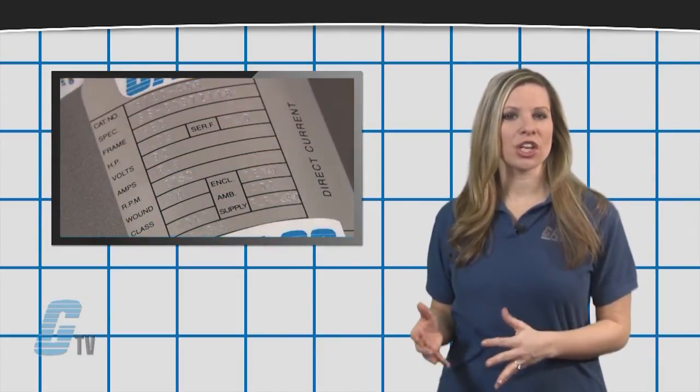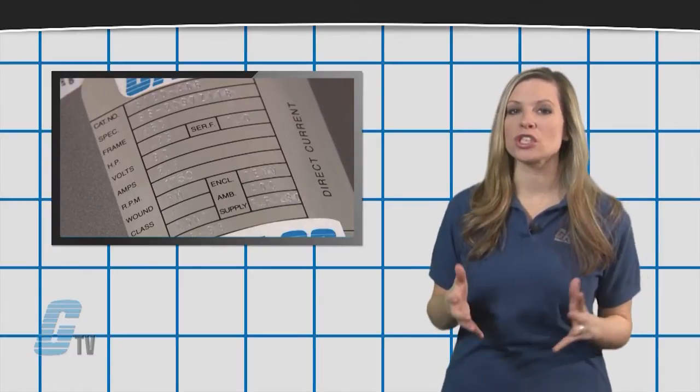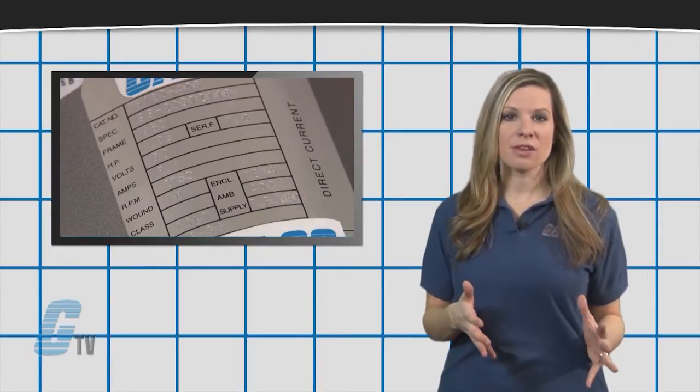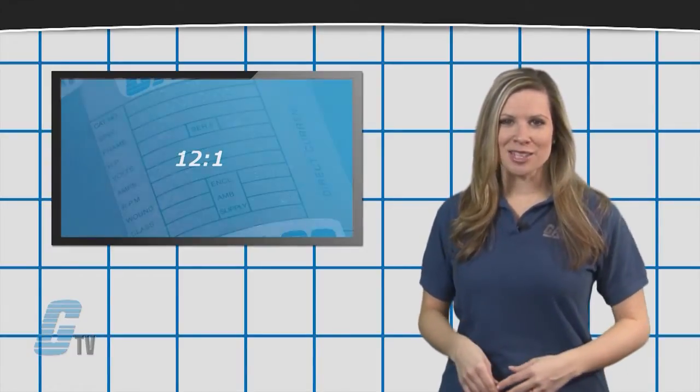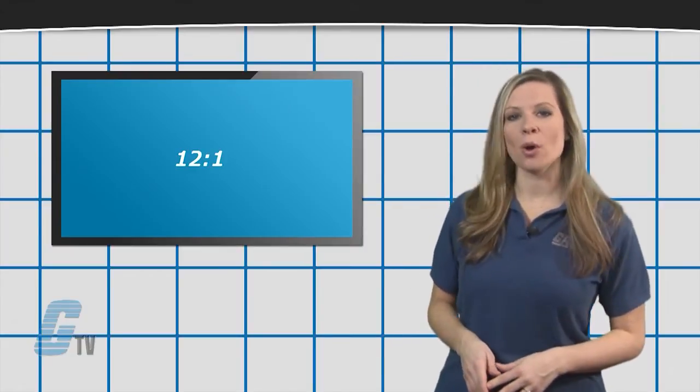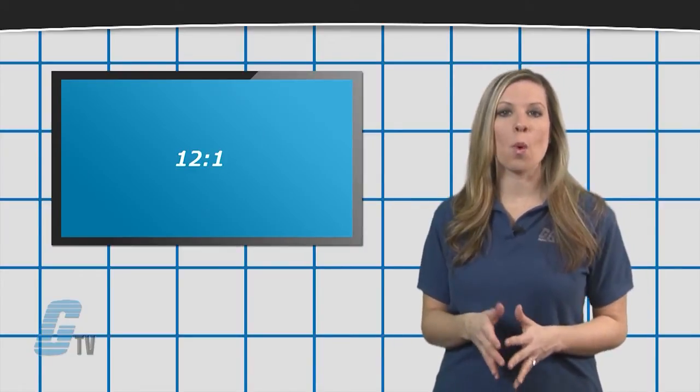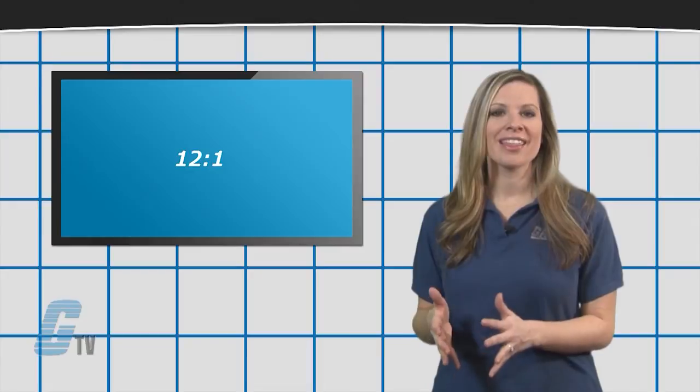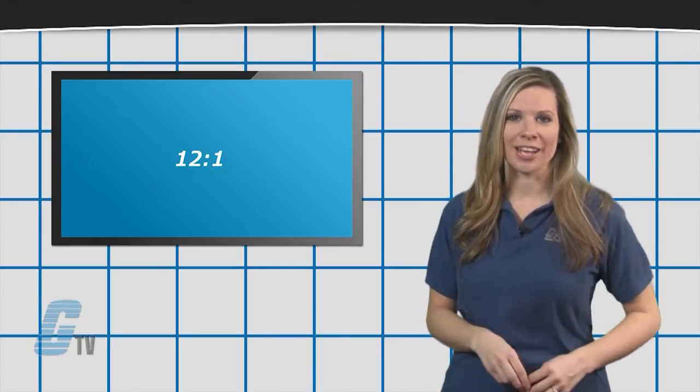there is a ratio on the name plate that will show the slowest speed the motor can go. If the speed range is listed as 12 to 1, the motor can continuously go 1/12th the base speed at full load.